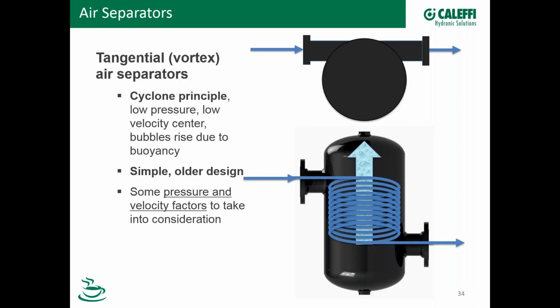I should also mention there's another type of technology called a tangential or a vortex air separator out there. Now, Caleffi doesn't make these, so I don't have a lot of detail about them. I'm not an expert, but I do know that they're based on a cyclone principle. At the center of that cyclone is a low pressure zone. So those bubbles will rise at the center of that product as the cyclone or the vortex forms. This is a simple, older design. It's been around for a long time. But something to know is that these are dependent on pressure and velocity. So if you have, for example, a very low velocity, you may not get a very good vortex. And if you don't have a good vortex, then you're not going to have very effective air removal.